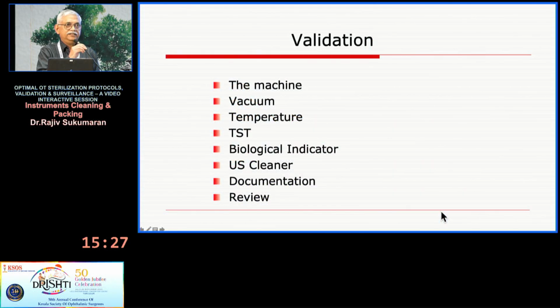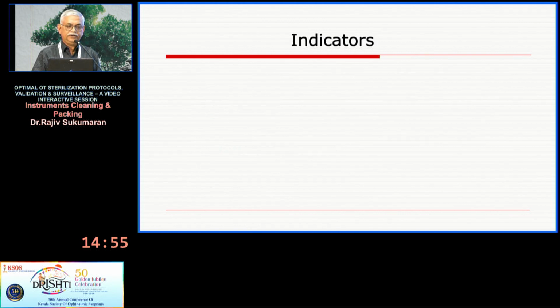So when it comes to validation, as far as sterilization is concerned, the machine is very important. You have to standardize the machine and check that it is working well. The vacuum part is very important, the temperature and the TST, that is temperature, saturation and time. And we have different indicators. The best one is the biological indicator. Then I showed you the ultrasonic cleaner and documentation. Above all, you will have to review your performance and the entire process periodically.